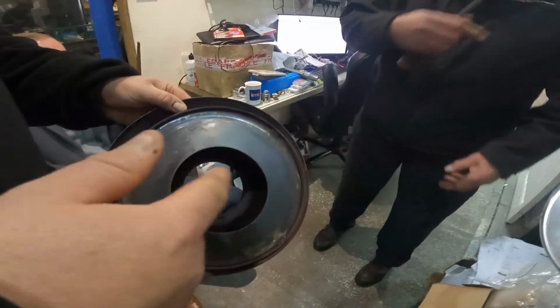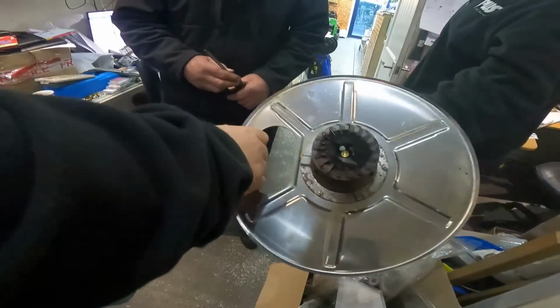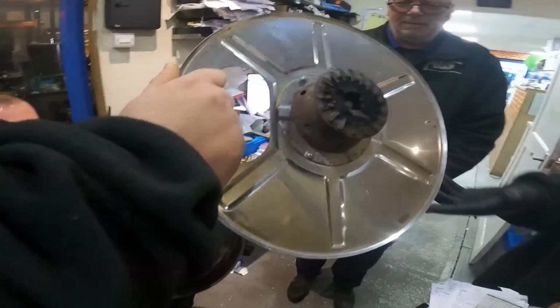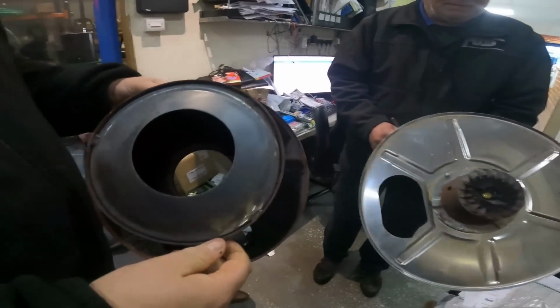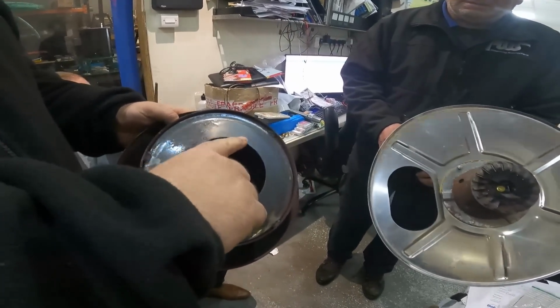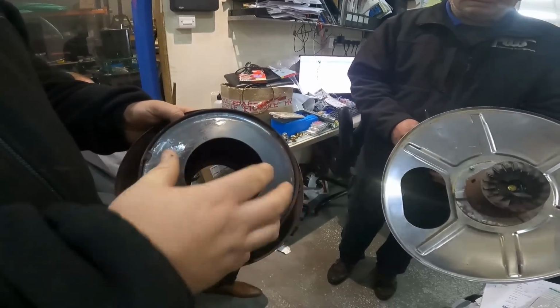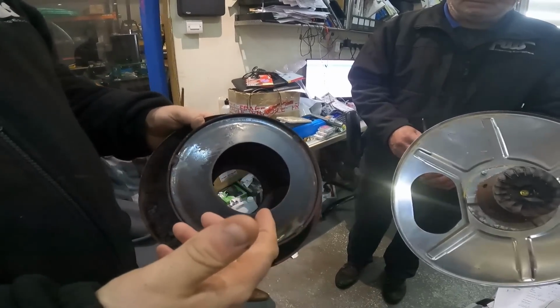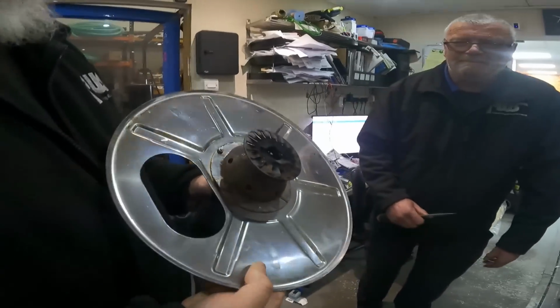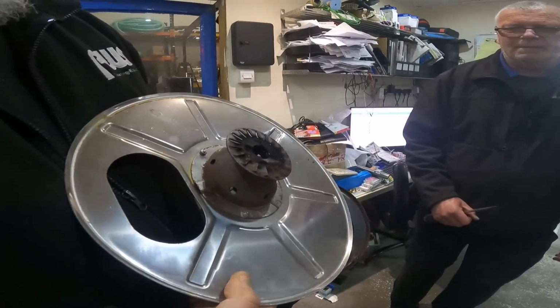What we're looking for in here is wear over time on the burner nozzle. The burner nozzle is this component inside here, the little brass one at the end. When the burner nozzle wears over time and you don't have it serviced regularly, which is not you, by the way, you have it serviced pretty regularly, it melts. And when this melts and doesn't have the correct shape, it makes it smoke really badly. What we've actually found here is the electrodes have either got knocked or moved a little bit, look. It's been in the van, and they're just not arcing properly.